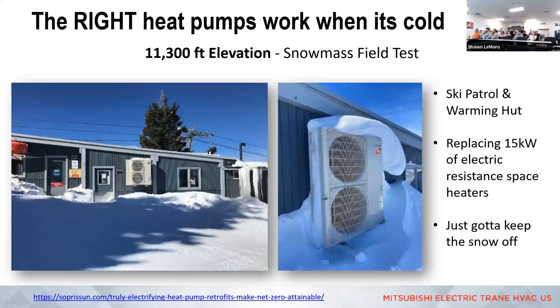Another application that was sort of a test case was up in Snowmass ski area. At the top of the ski lift, that's 11,300 foot elevation, we were able to put in a system that replaced 15 kW of electric resistance heat. So it's one third the power that has to go into heating that building as opposed to the 15 kW electric resistance heat. So that's a win.